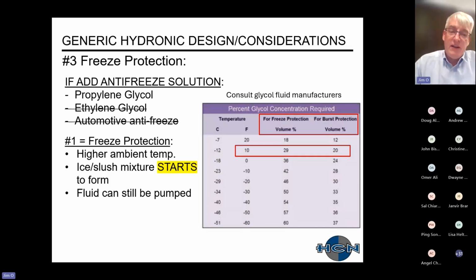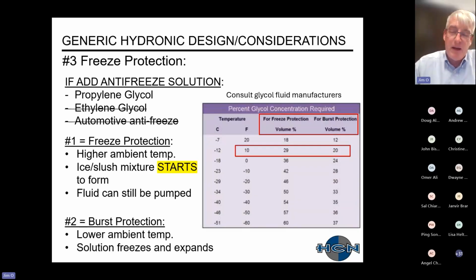Freeze protection is a higher ambient temperature. This is the temperature where the glycol mixture, which is mixed with water, will start to turn to ice and slush. At this time, it still can be pumped, but as the ambient temperature drops further, you'll hit what is called burst protection. This is at the lower ambient temperatures, when the solution does freeze and expand, and as the name implies, it will burst.